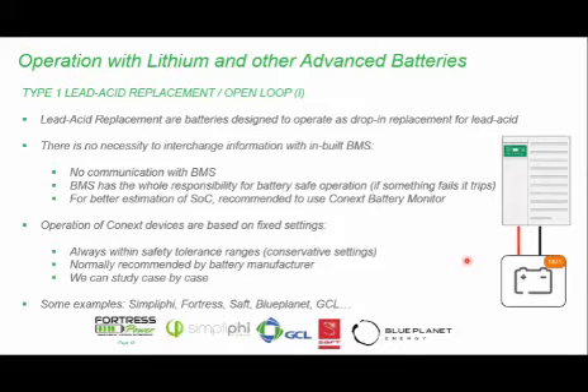So you typically use open loop settings in this kind of scenario. In open loop settings, you might not be able to enjoy the full extent of the batteries because, as different transitions happen for the battery, it varies with time. Sometimes the ambient temperature can rise, which would typically reduce the performance of the battery. Sometimes your battery might even want you to give it more current to charge, or tell you that you can use more out of it, so the discharge current can even increase. But because the battery is not communicating with your inverter, you do not have this sort of leisure. So the settings you typically input on the inverter itself are more conservative values, because you want to try and be within good limits all the time. You might not be able to use the full extent of the batteries.